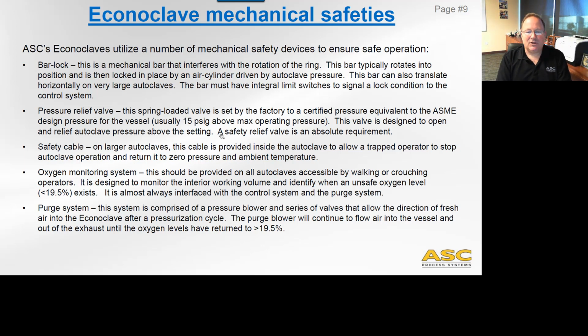Pressure relief valve, it's a spring-loaded valve that's basically set by the factory to a certified pressure equivalent to the ASME design pressure for the vessel. Now, on an ASC autoclave, the working pressure of the autoclave that we set is always 15 psi below the maximum operating pressure of the pressure vessel. So the relief valve is generally going to be set 15 psi over our maximum operating pressure. This valve is designed to open and relieve at that pressure setting. And basically every pressure vessel on Earth has got to have a safety relief valve. It's mandatory.